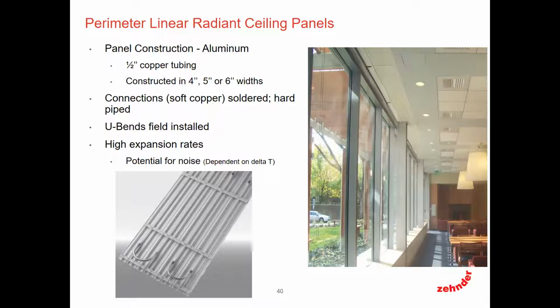Things to be aware of and pitfalls. These are copper aluminum panels. So depending on what your water temperatures are, depending on what your steady state is, if you were to hit this with hot water, say 180 degrees or 200 degree water, that copper tube inside will expand and contract. And as it expands and contracts, it will do it at a different rate than, say, the aluminum saddle. So I have seen applications where the copper tube actually rubs on the aluminum saddle itself and creates a pinging. The good news is it will stop when it hits steady state and warms up, but just be aware that that's one of the things that I've seen in the field.